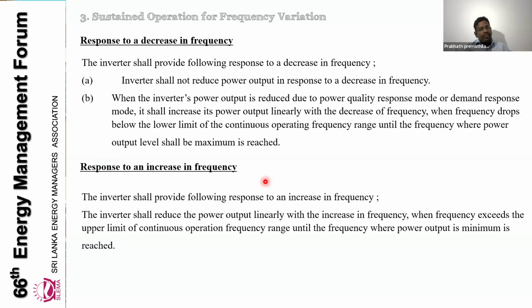So likewise in grid forming inverters also, we can easily respond to an increase in frequency, but for a decreased frequency, the inverter should operate in the power quality response mode. If the inverter is operated in the power quality response mode or any kind of demand response mode as per the system control center, they will stop that mode, and they will inject power output linearly until the frequency reaches the lower limit of the continuous operation frequency. Likewise, the inverter can itself ride through the frequency disturbance as well.